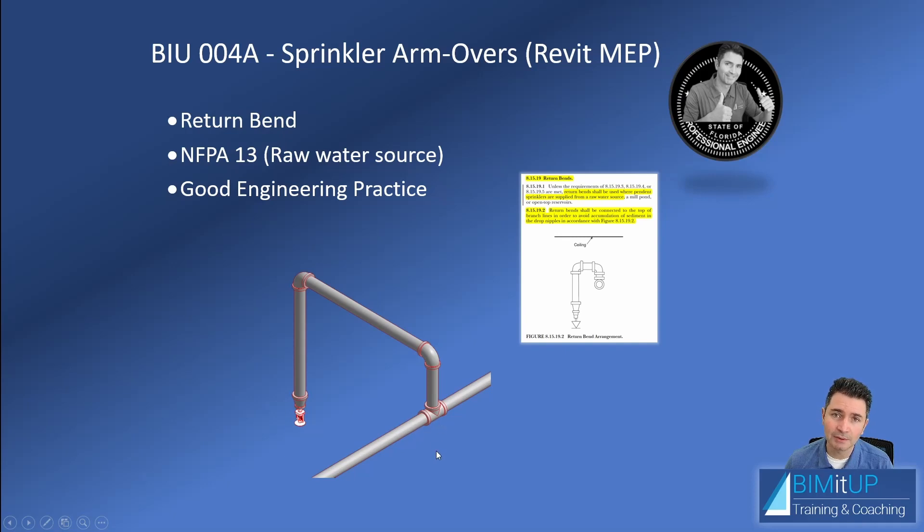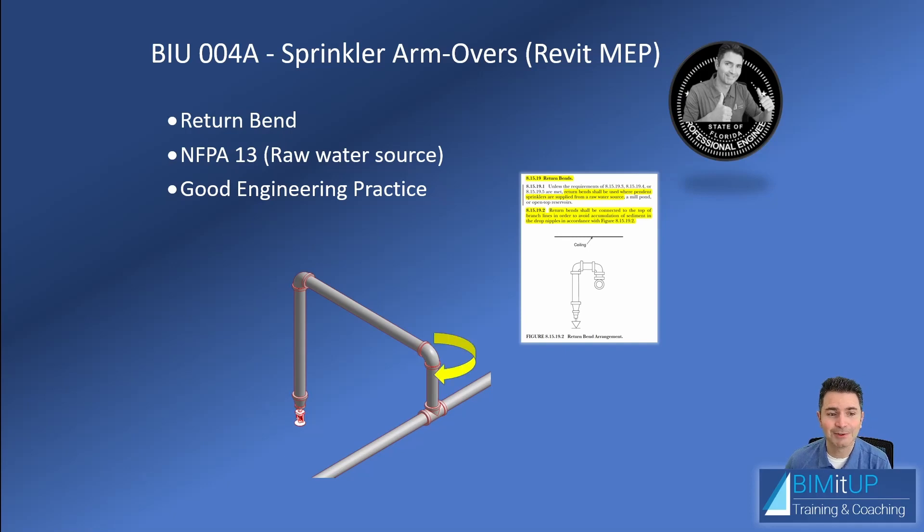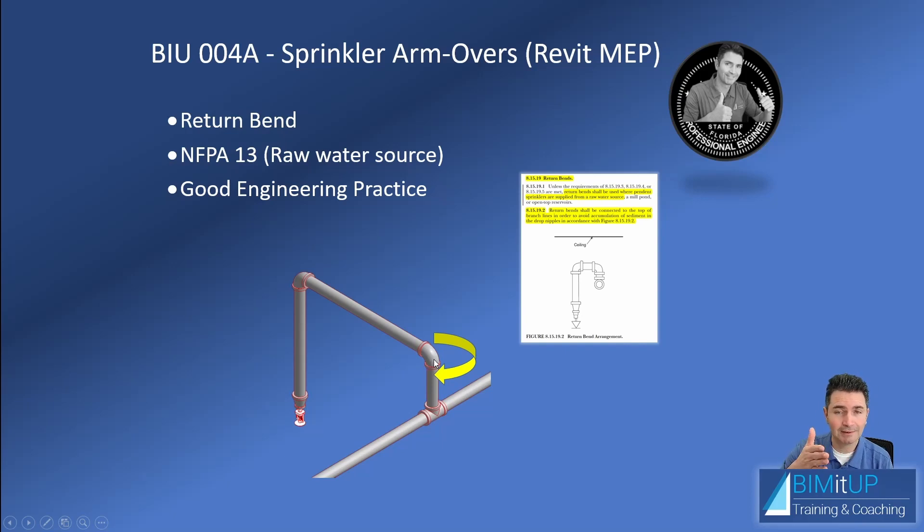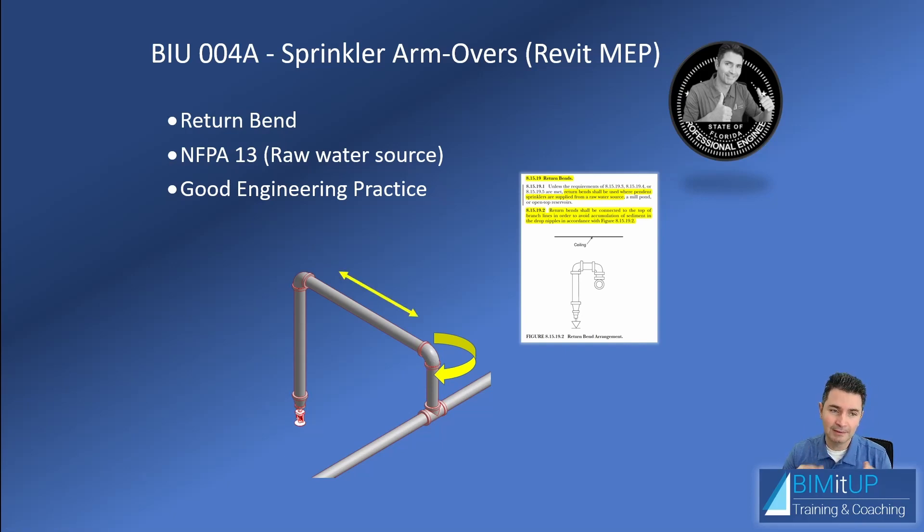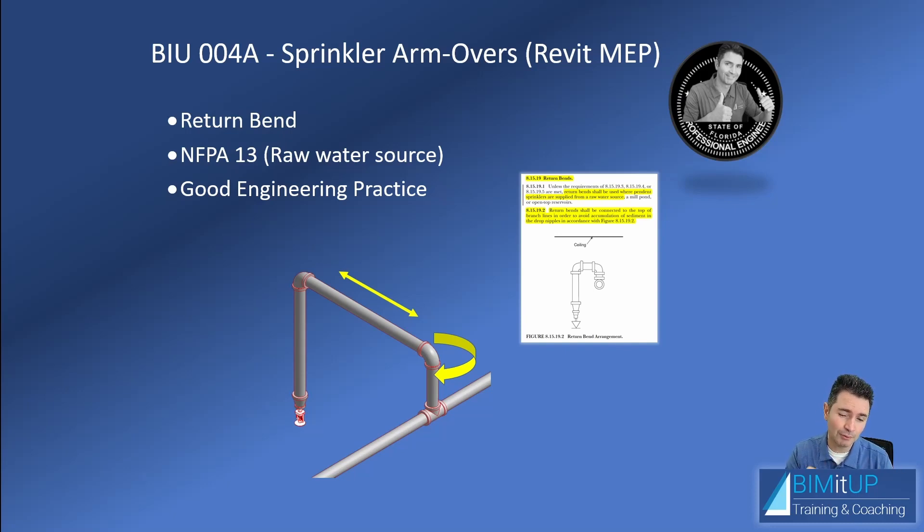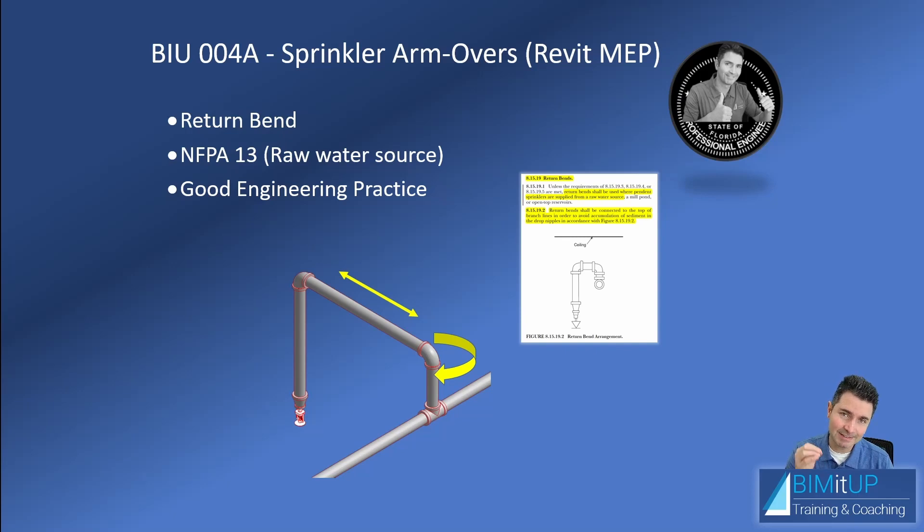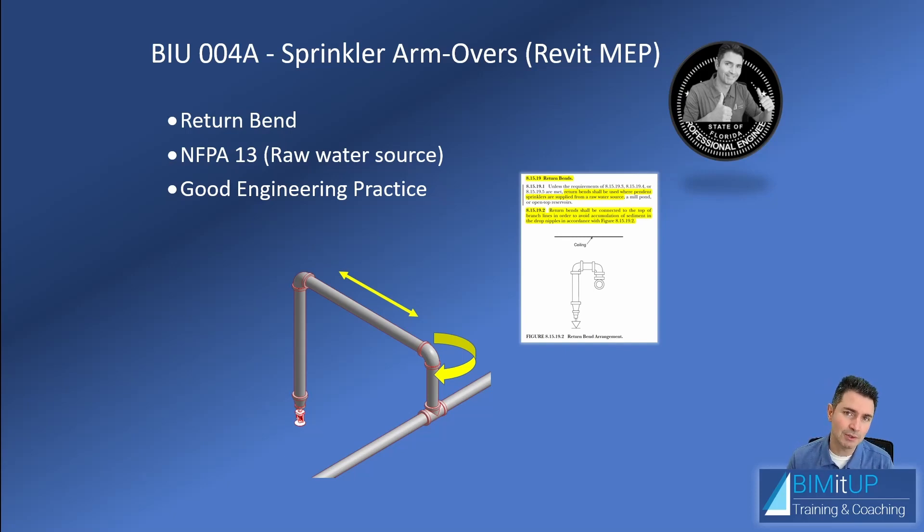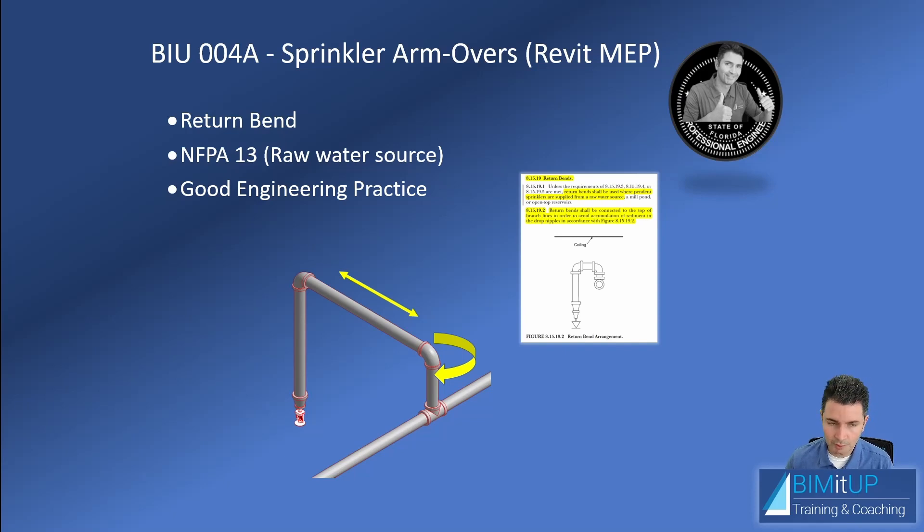You will have a lot of dirt and sediments that could make it all the way down to your sprinkler and clog your sprinkler. A bonus that you get out of this is that you have your swing joint here that allows you to rotate, and you also have that horizontal piece that can shrink or stretch so you can have your sprinkler located exactly where you want it, which is typically in the center of the ceiling tile or at a very specific location.